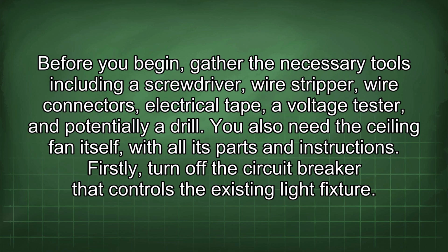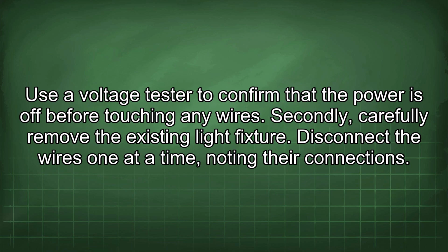Firstly, turn off the circuit breaker that controls the existing light fixture. Use a voltage tester to confirm that the power is off before touching any wires. Secondly, carefully remove the existing light fixture. Disconnect the wires one at a time, noting their connections.